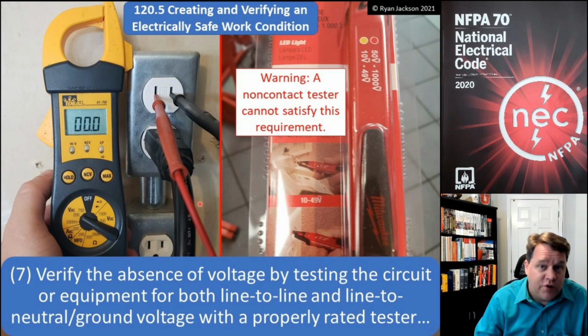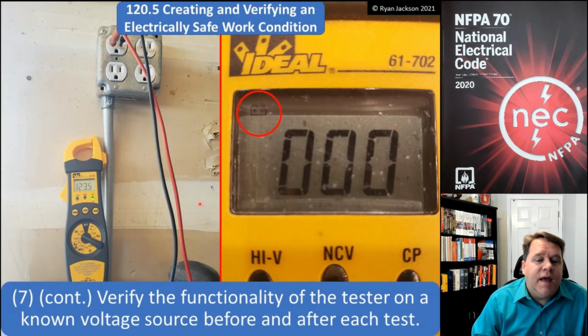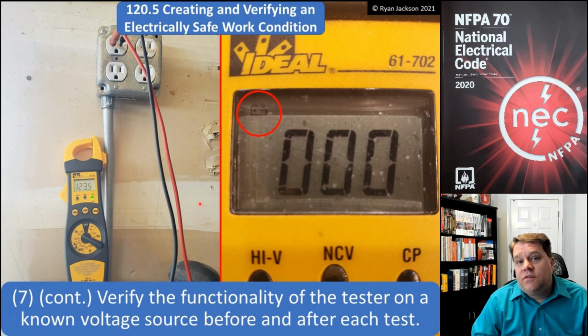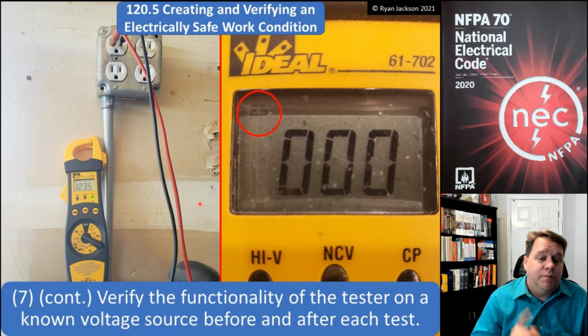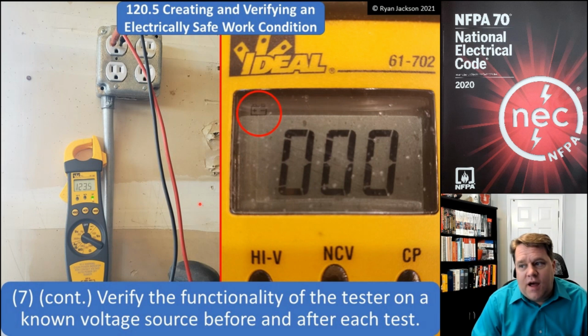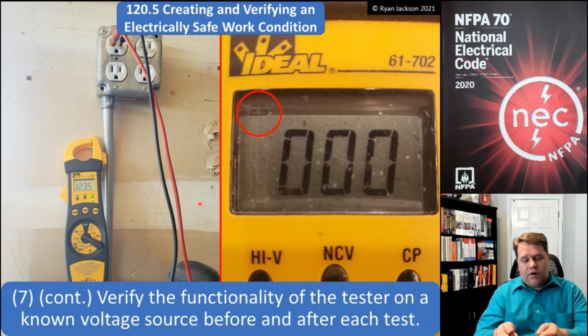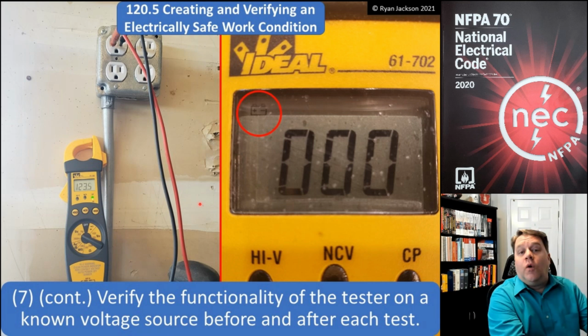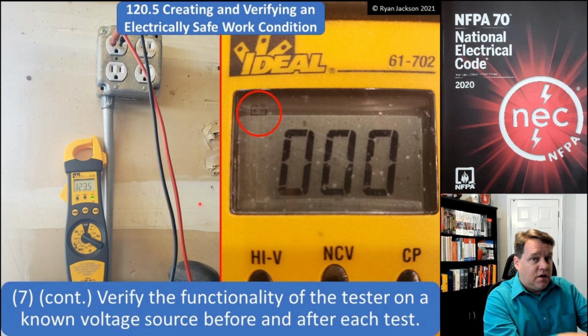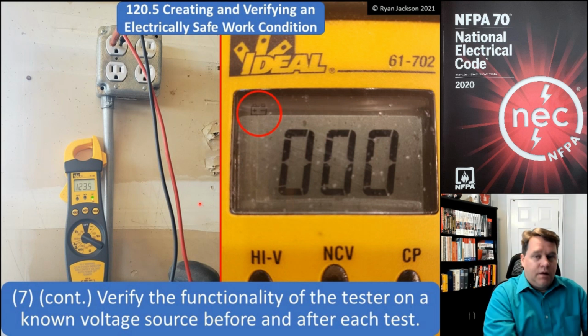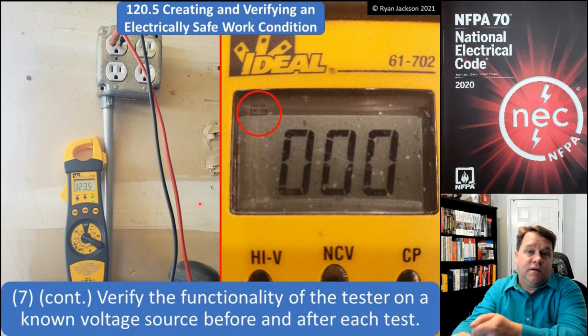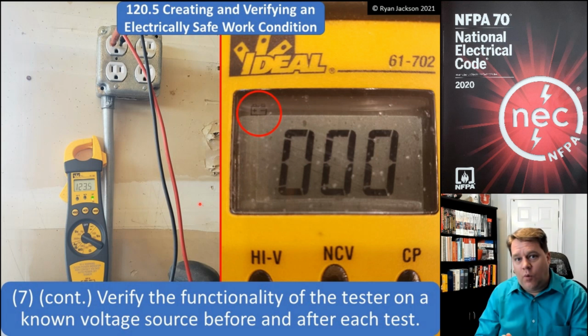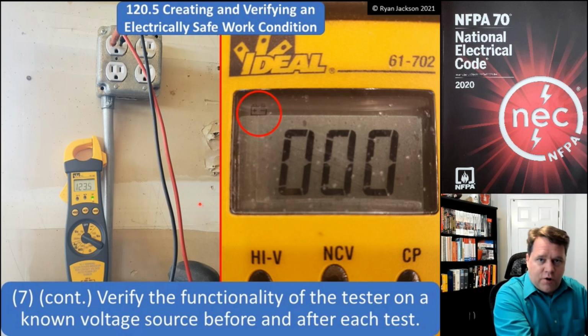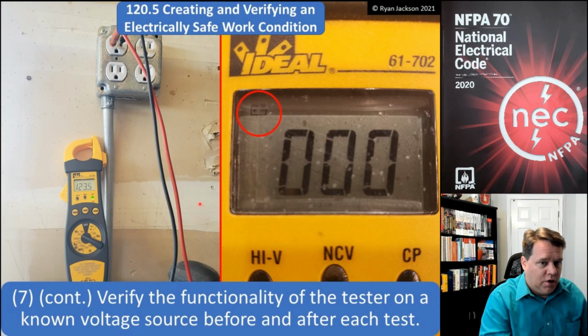We're going to test the circuit, and we need to test the test equipment. We need to test it before and after each test, and this is often called a live-dead-live test. We're going to take our tester, plug it into something that we know is on and working, and verify that our tester actually works. Then we're going to verify the absence of voltage on the circuit that we're working on, and then we're going to do what? We're going to check our voltage meter one more time and make sure it still works.